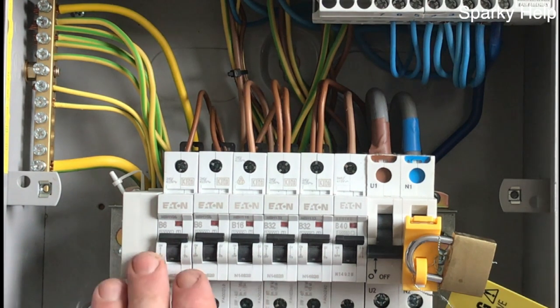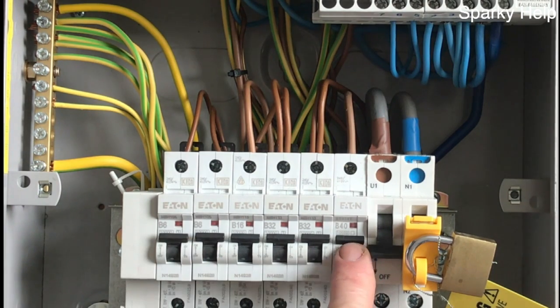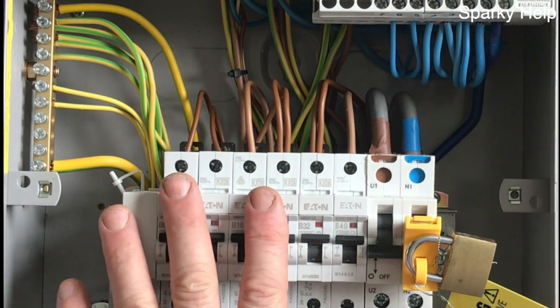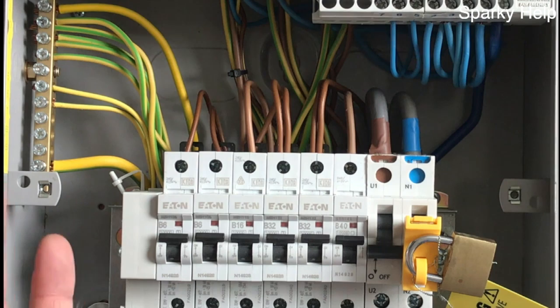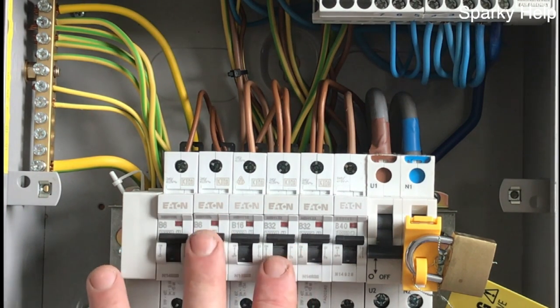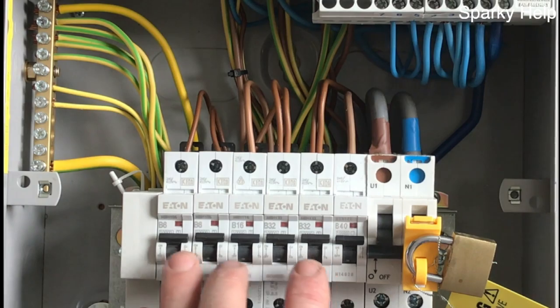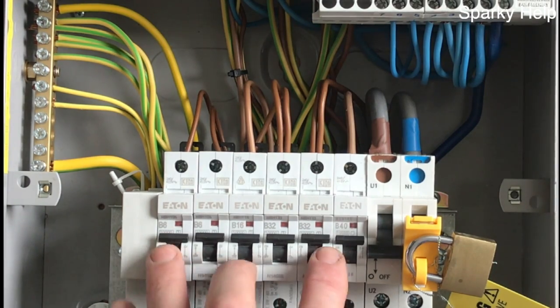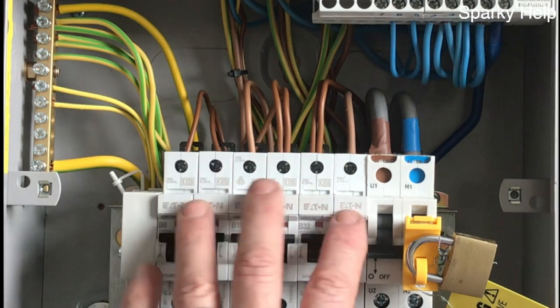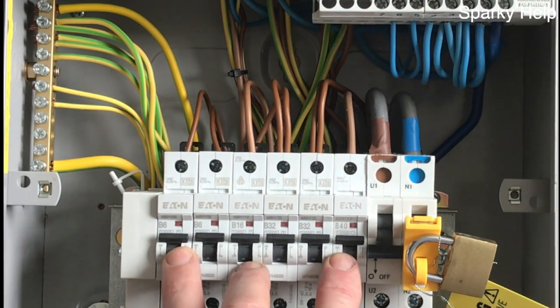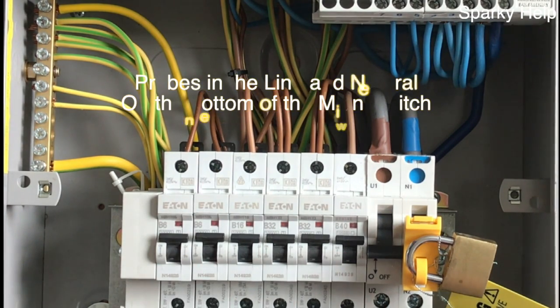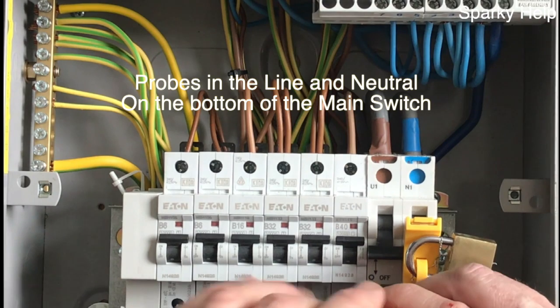So what we can do is we can switch the breakers off. We don't need to disconnect anything, which is always the best thing when doing testing. Try not to remove as much as possible. Leave it all intact. So we do know that the fault is between line and neutral. So all we need to do is test either one side or the other and find which circuit has got the fault on. So we can leave it on there.